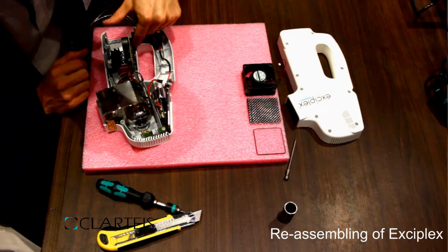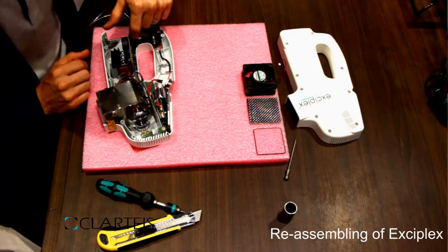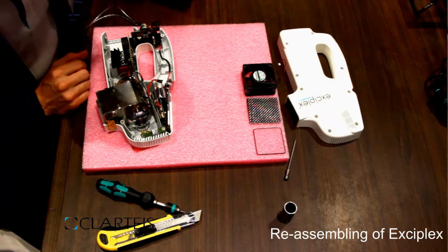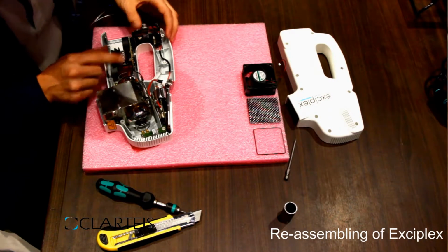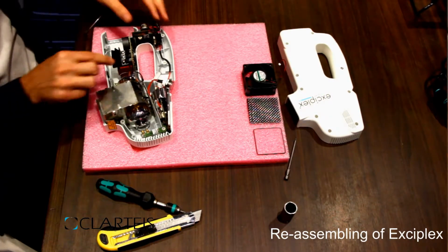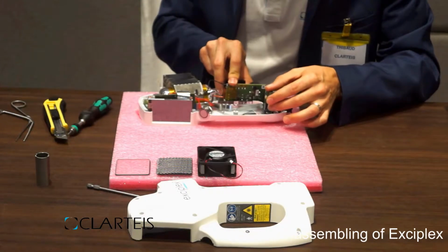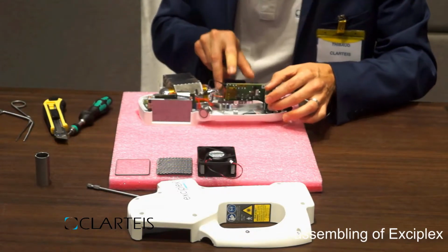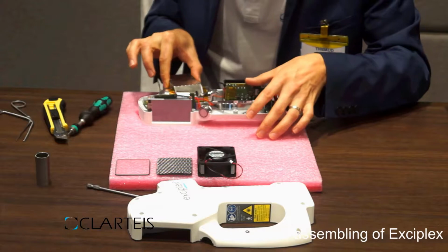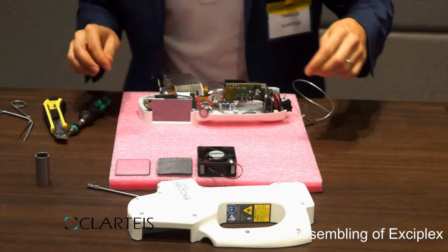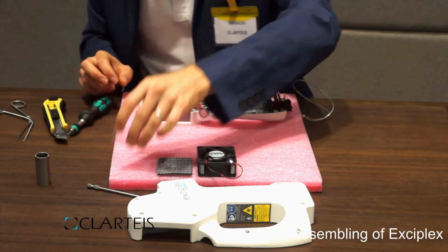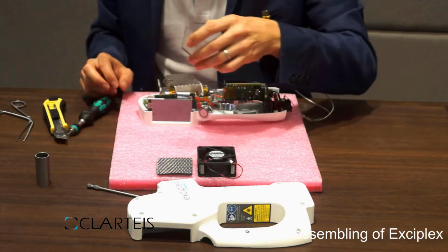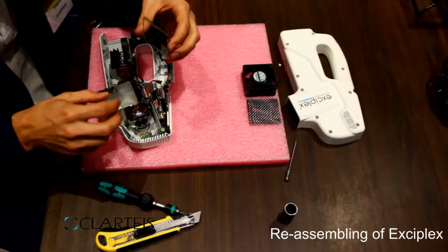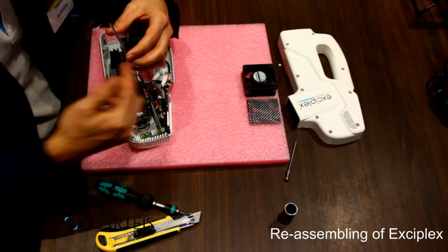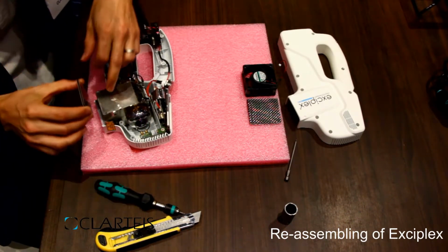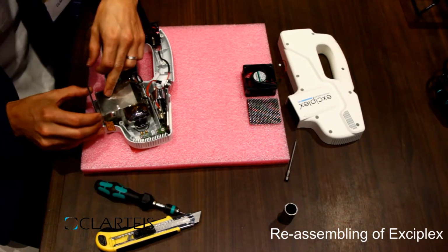Be careful with this connector, make sure that you won't miss any connection. And now you just see that the HVB board is well in place. The bulb is well in place also. So now we can put the output window. As you see, the thinner part needs to be inside the device when you slide it down to the shell.